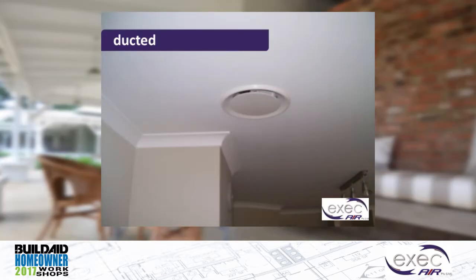I mean, theoretically, the aircon, no matter which installation it is, would be circulating the air in a space. Yes, it would. If you take a mid-wall split, for instance, your return air and supply air will be exactly on the same unit. Ceiling cassettes, more or less the same, where the air will return to the middle of the unit and be forced out through the vents on the side of the units. Ducted units, you will have a return air grill, which will take in return air. It will pass through the indoor unit and it will come out through the diffusers, as you can see on the monitor there.